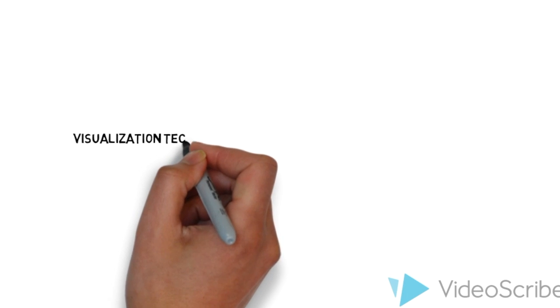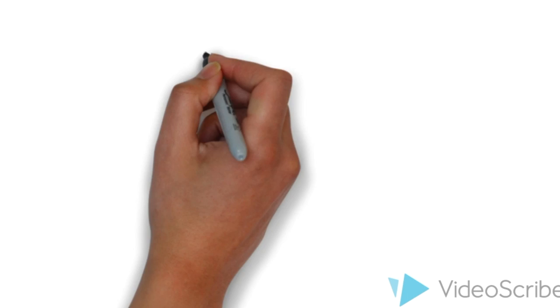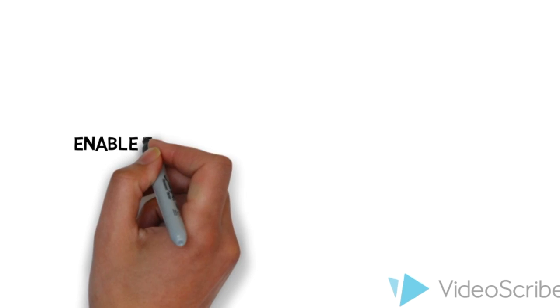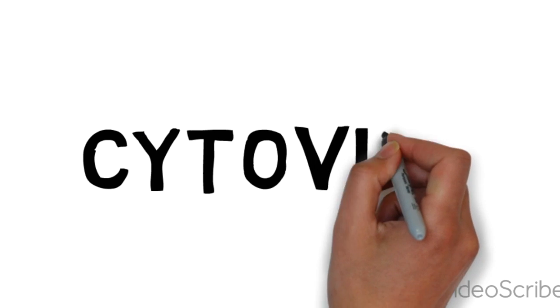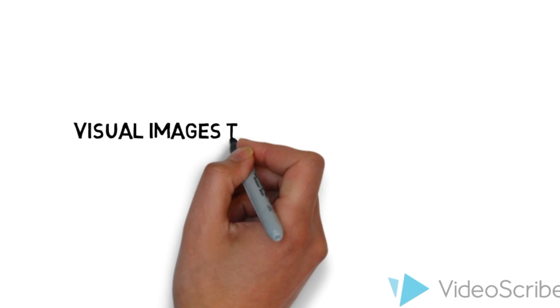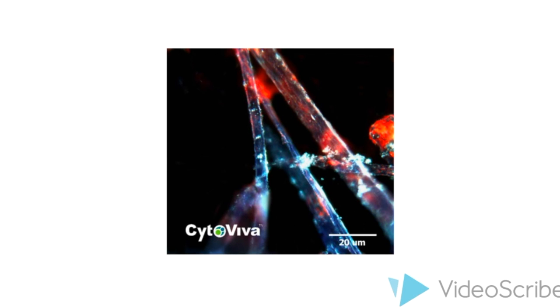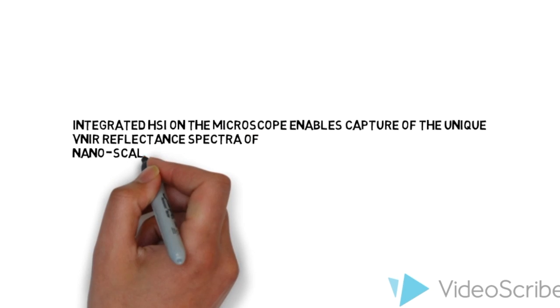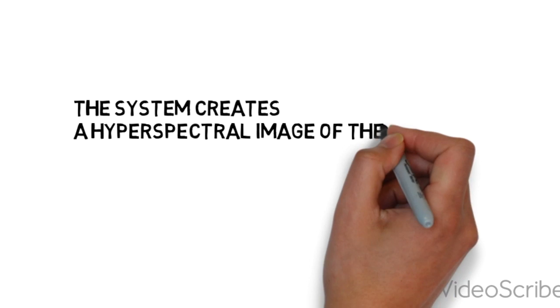Hyperspectral microscopy is an advanced visualization technique that combines hyperspectral imaging with state-of-the-art optics and computer software to enable the rapid identification of materials at the micro and nano scales. A technology called Cytoviva is based on this principle and allows us to produce visual images that have 7 times the intensity of standard dark field microscope optics. Integrated hyperspectral imaging on the microscope enables capture of the unique VNIR reflectance spectra of nanoscale materials within a wide range of biological and composite environments, creating a hyperspectral image that enables nanomaterials to be spectrally characterized and mapped throughout the entire sample.